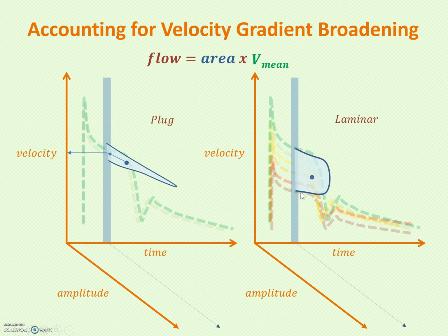And when you do the centroid here, get the center of gravity of the amplitude, you can see that the centroid frequency is much less than the max frequency in green here. So they're dissociated. In a blunted parabolic flow profile, as in a peripheral artery, the max to mean velocity is always very close to 2:1. It's almost always double. So when you calculate flow based on the max velocity in a peripheral artery, you quite often double the actual value.